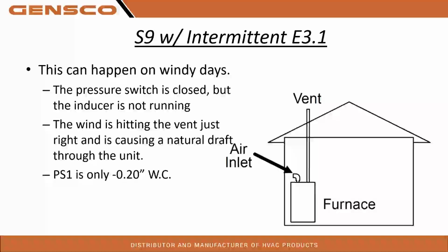Also, if you have to run the air inlet out, for most jurisdictions, you have to run it all the way out with the vent or in the vent's area. It has to be on the same side of the home. So in this situation with this air inlet in the garage or what have you, if we needed to run an intake, we'd have to run it on the same side of the building. We could not run the intake air over here because that can affect how air moves through that furnace, right? So that's one thing to keep in mind with the S9 furnaces, has to vent or intake on the same side. Okay, but high wind can do it.